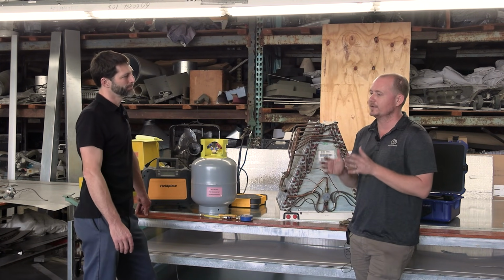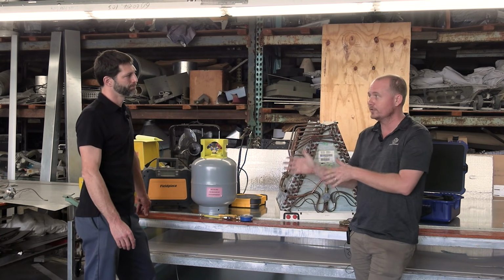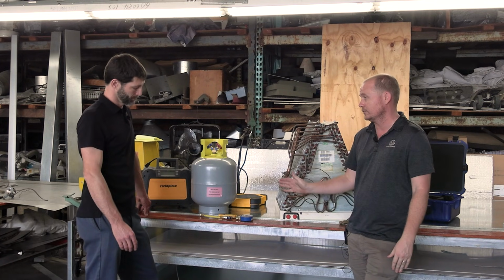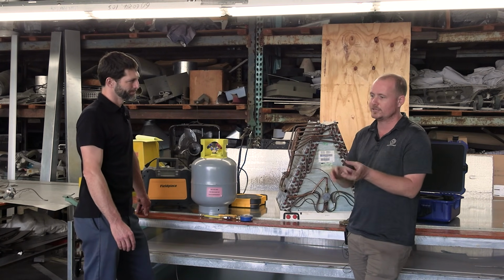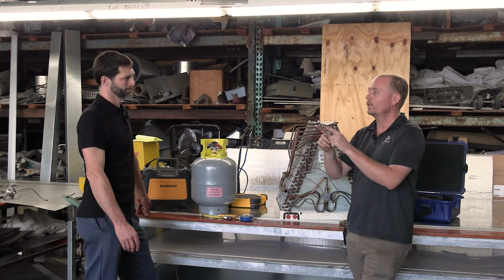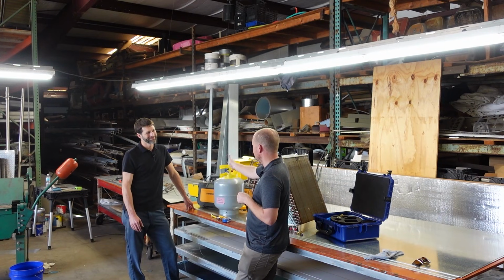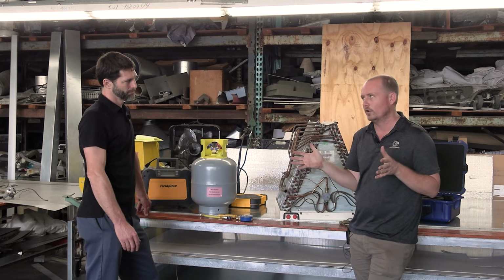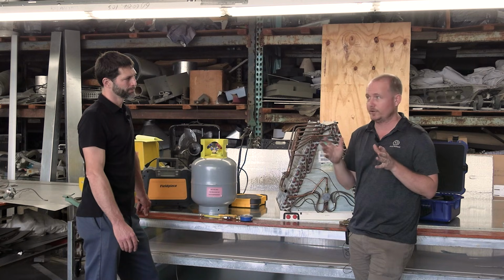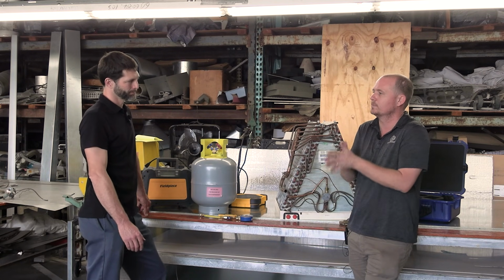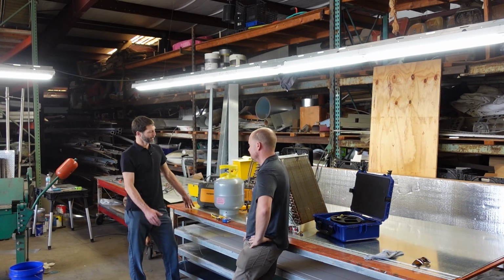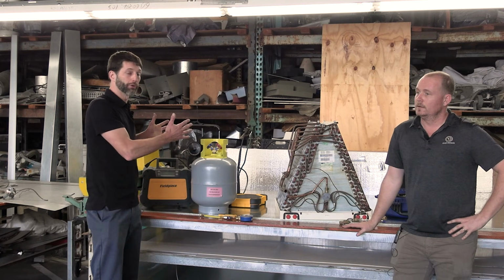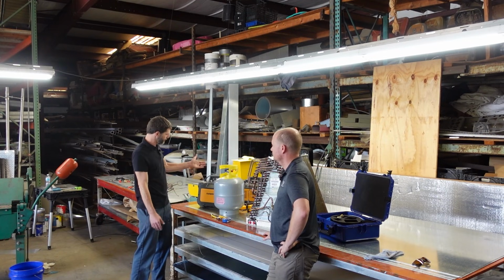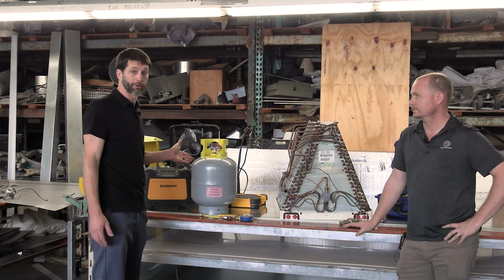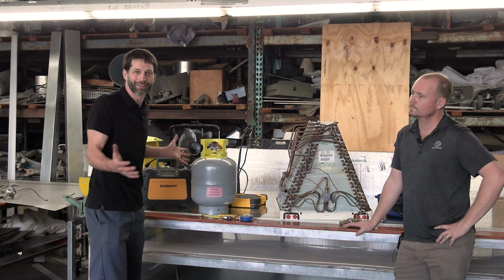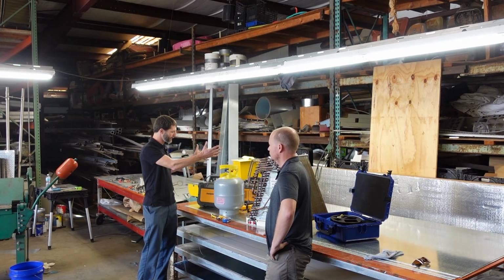Right. And so again, our goal is to do our due diligence so that we are not intentionally venting refrigerant. Beyond that, the little bit of loss that you have with disconnecting and purging, or that little bit that's in between the recovery machine and the recovery tank, those are all acceptable as long as you're doing everything you can to prevent the venting of refrigerant. And I always try to keep that hose short. There's no need to have a 5-foot hose going from the recovery machine to the recovery bottle, because in the end that's going to have refrigerant in it.